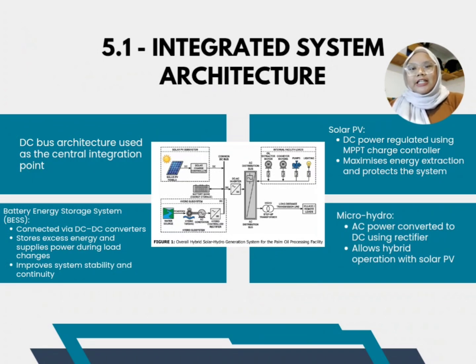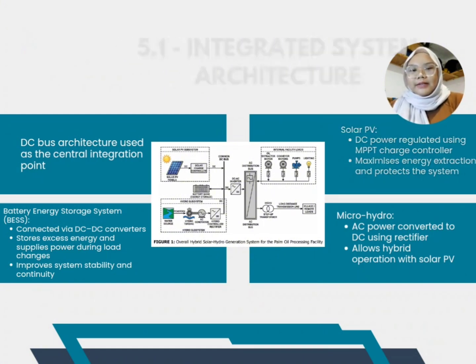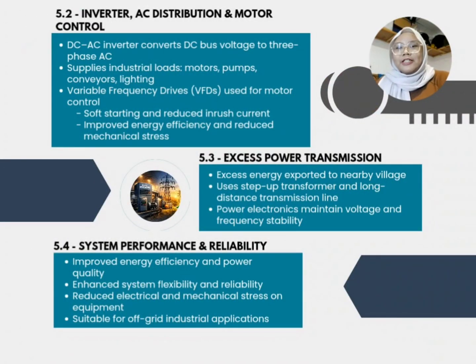A battery energy storage system is connected through a DC-DC converter to store excess energy and supply power during load changes, improving system stability. The stabilized DC bus voltage is converted into three-phase AC using a DC-AC inverter. This AC power supplies industrial loads such as motor, pump, conveyor, and lighting. Variable frequency drives, or VFDs, are used for motor control to provide soft starting, reduce inrush current, and improve energy efficiency. When excess power is available, it is transmitted to a nearby village through a step-up transformer and a long-distance transmission line. Power electronics ensure that voltage and frequency remain within acceptable limits before transmission. Overall, power electronics improve energy efficiency, power quality, system flexibility, and reliability. They also reduce electrical and mechanical stress on equipment, making the system suitable for off-grid industrial applications.